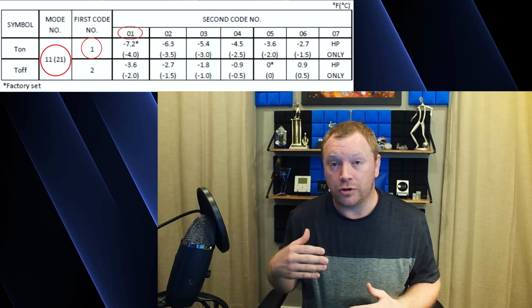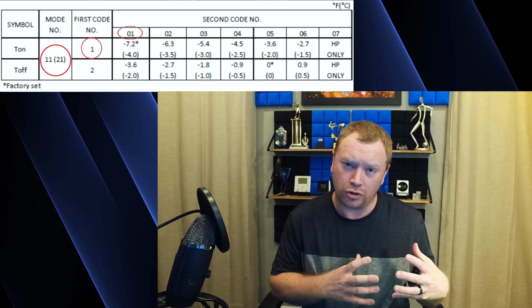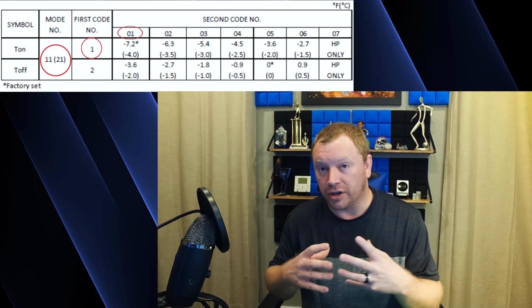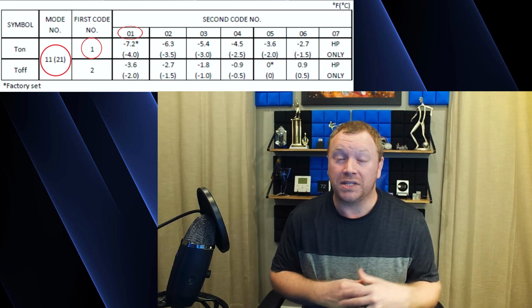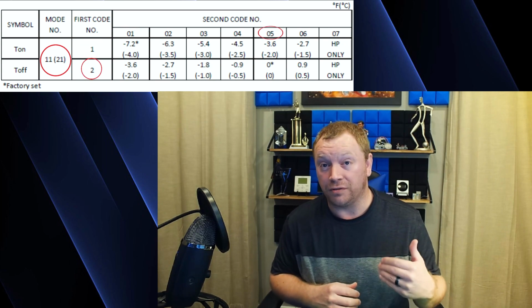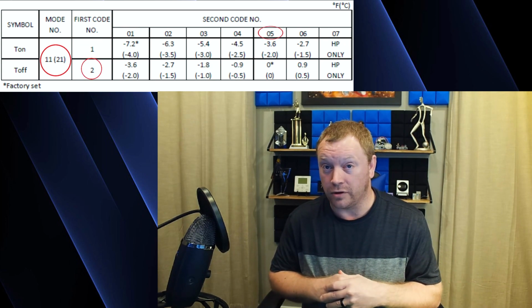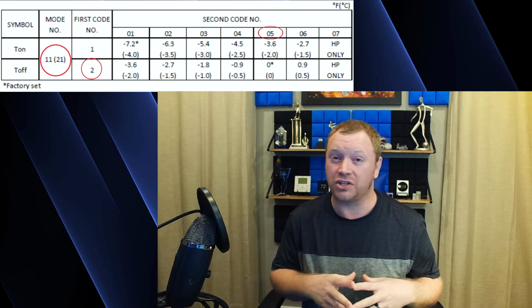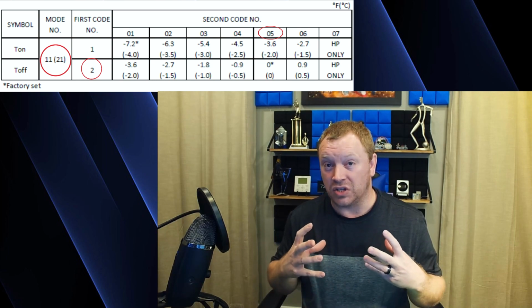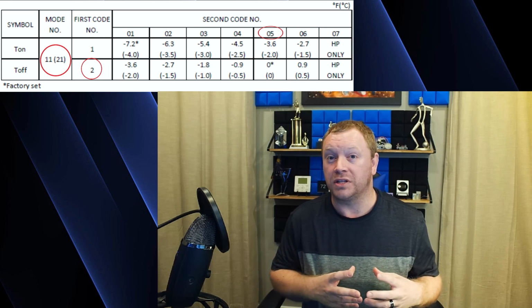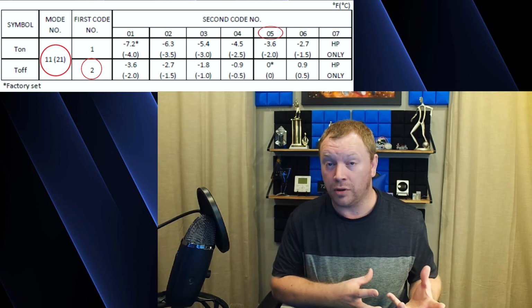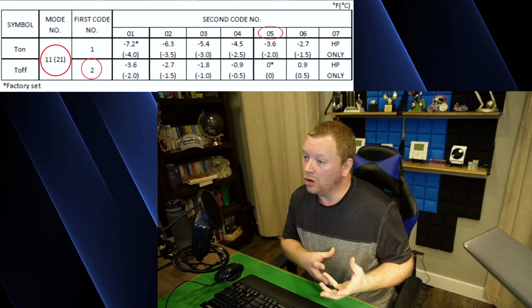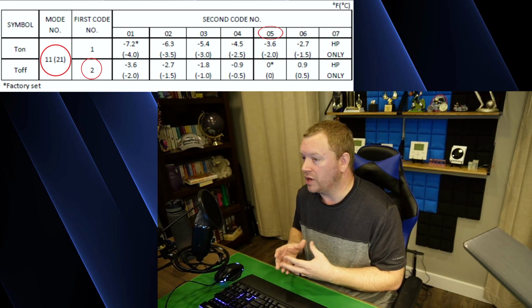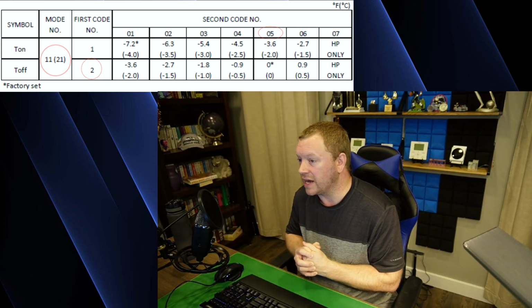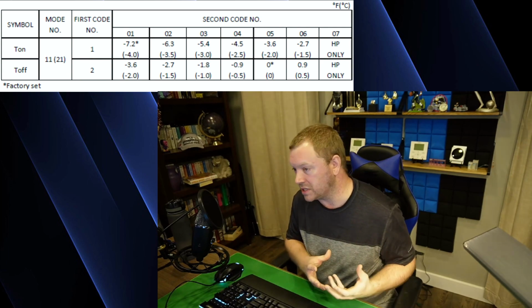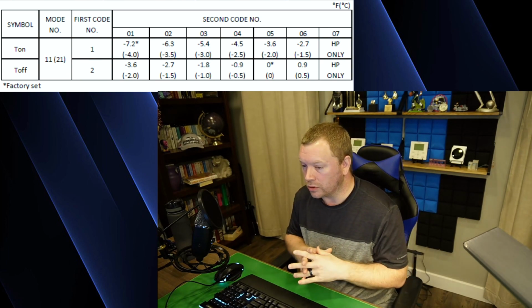Then you need to program your T-off temperature. So at what temperature do you want your gas to then shut off? And that's mode 21, setting 2. Now 2-05 is the default with the gas furnace. So if you look at this chart here, you'll see 2-05 is a 0. That is 0 degrees below the set point, which means when the gas comes on for the heat pump, it is going to recover all the way back up to the set point, and then it's going to finally shut off the gas.